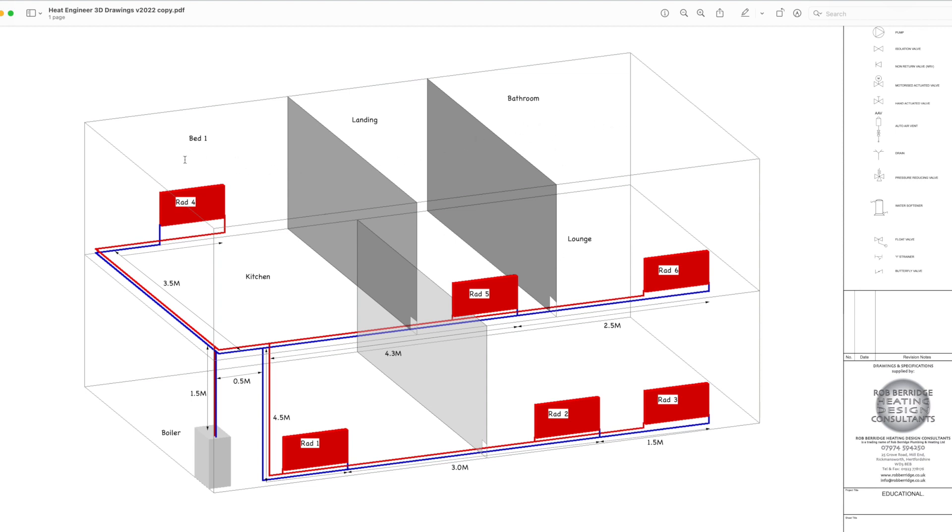If this room, bedroom one there, and the landing is both at 21 degrees, you don't have to put the wall in, but what you do have to put in is the square meterage of the floor area and the square meterage of the floor area of the landing independently. Otherwise, you won't be able to size your radiator. So you literally would just take this out.